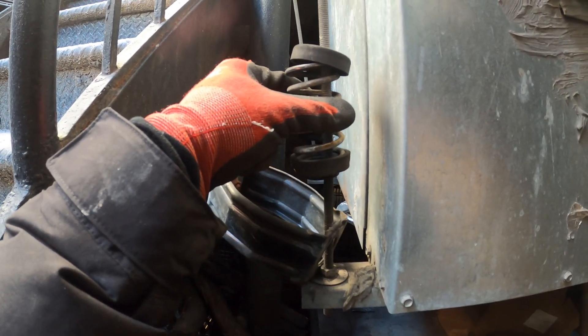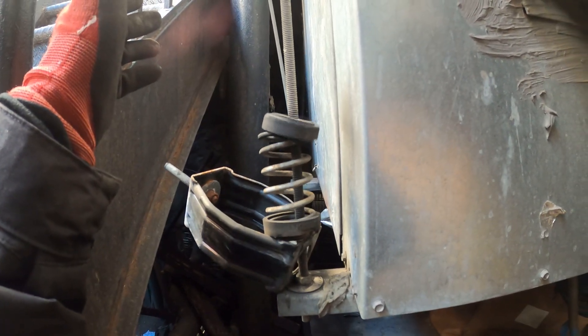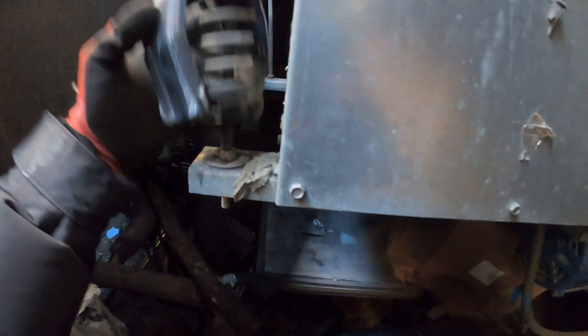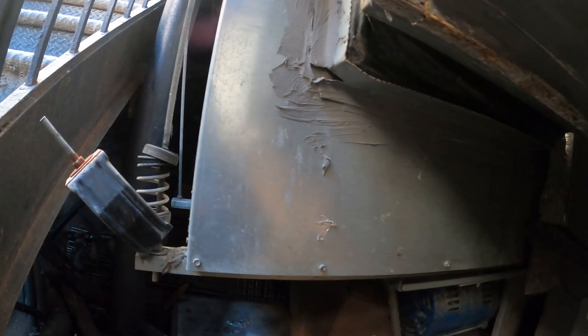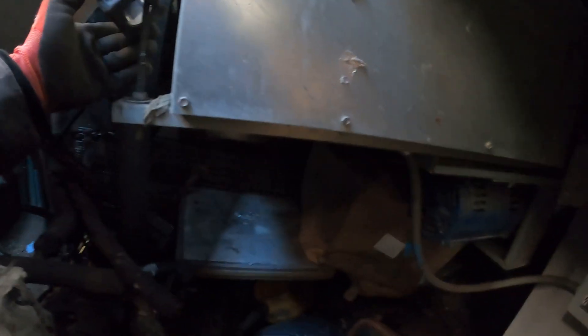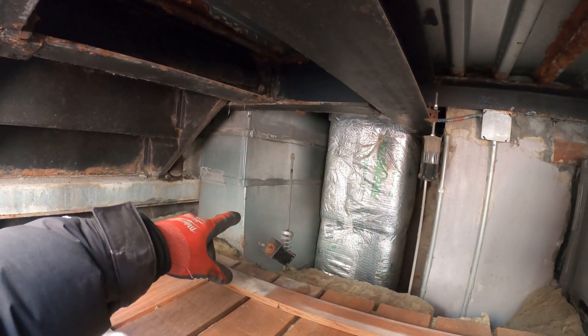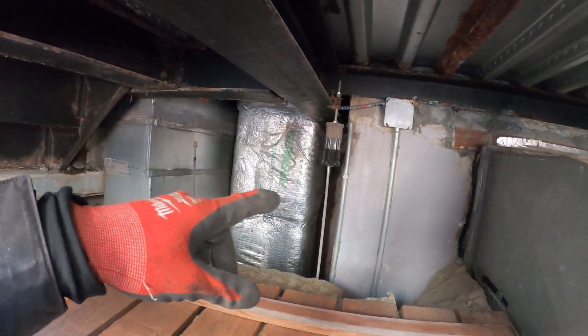It's making quite some noise. That alone already helped with the noise. The hanger broke. Power off — you guys can't see that I just turned off the disconnect. This whole thing came down. Look at that — one threaded rod broken, another one broken, and a third one broken there. Wow. Got only one support holding this whole thing up.